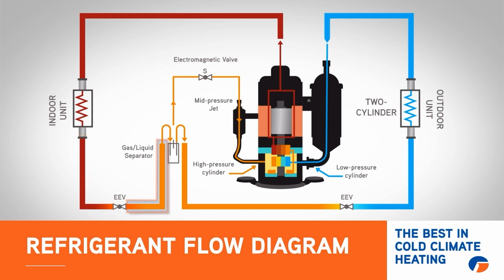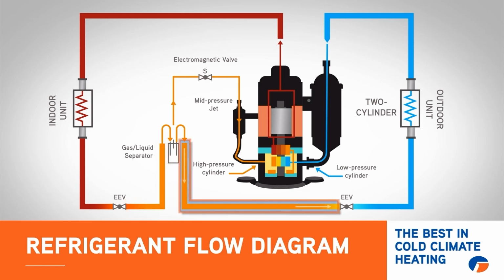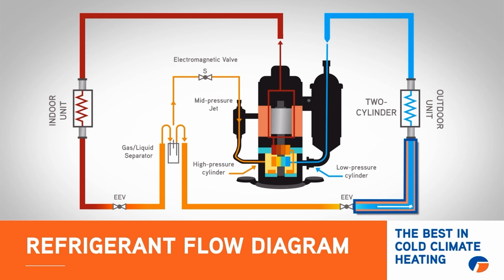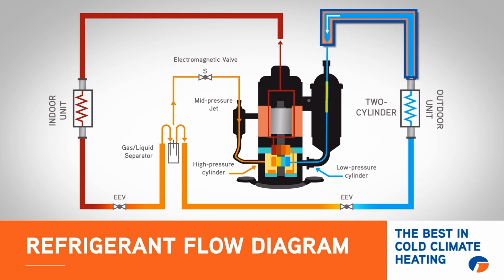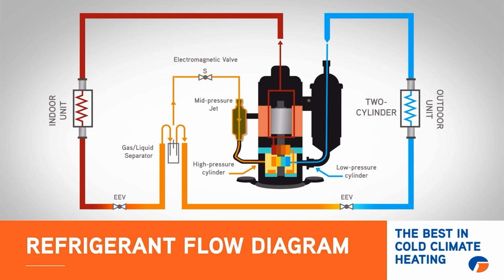This will subcool the liquid some before it flows into the bottom of the gas liquid separator. The cool refrigerant will then flow from the bottom of the gas liquid separator to the primary EEV to flash refrigerant into the outdoor coil, where the refrigerant will boil off into a gas, absorbing heat. Then the refrigerant flows back to the compressor into the low pressure cylinder. In cold climate heating, the electromagnetic valve will open and allow refrigerant to flow from the top of the gas liquid separator through the solenoid into the mid-pressure jet into the high-pressure cylinder of the compressor, effectively compressing the refrigerant a second time and increasing the discharge gas temperature.